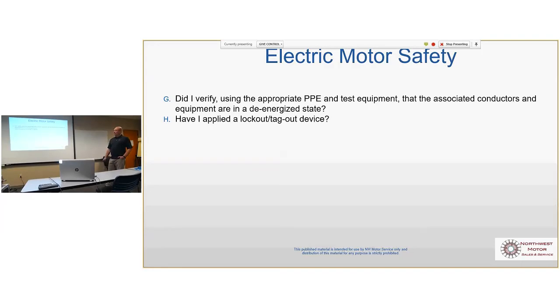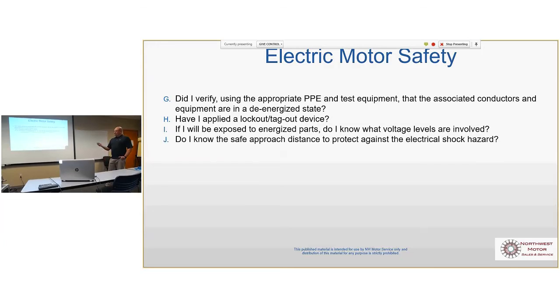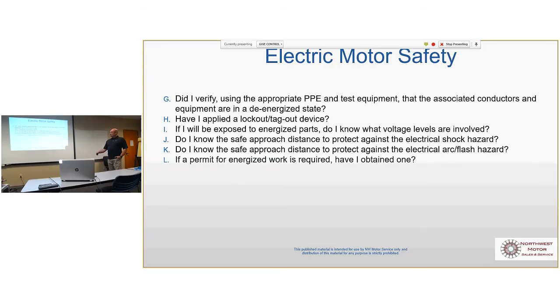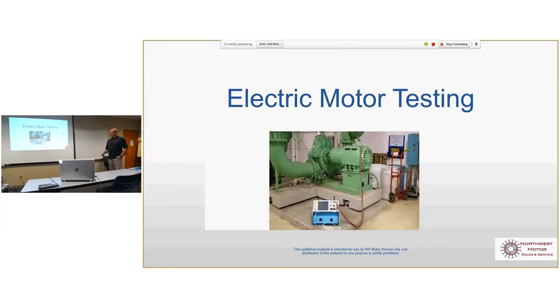And then use the lockout tagout device. And then safe approach distances. A lot of the newer stuff will have labels on the doors that tell you what category of clothing you should be wearing and what the arc flash boundary is around the equipment. And I'm sure you guys work at all different kinds of places, so I'm just saying, make sure you have the right permits for wherever you're at. And then we'll get into the guts of the thing.